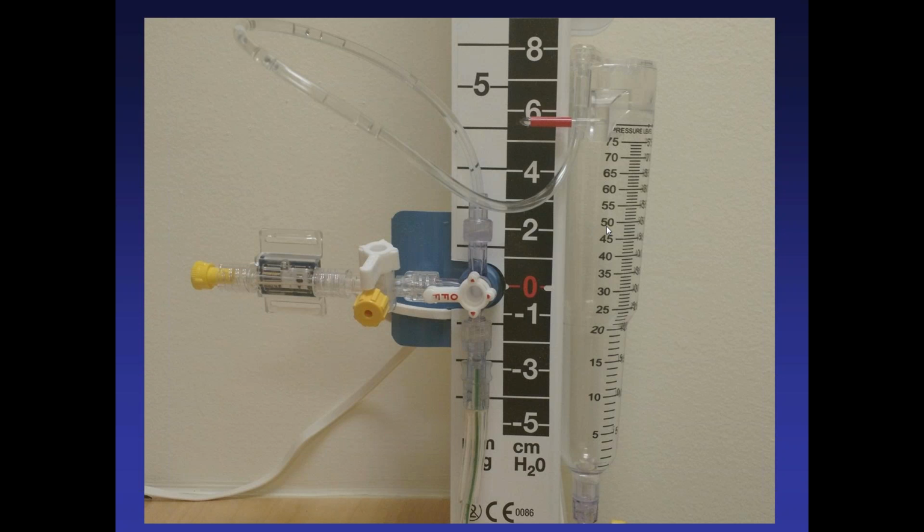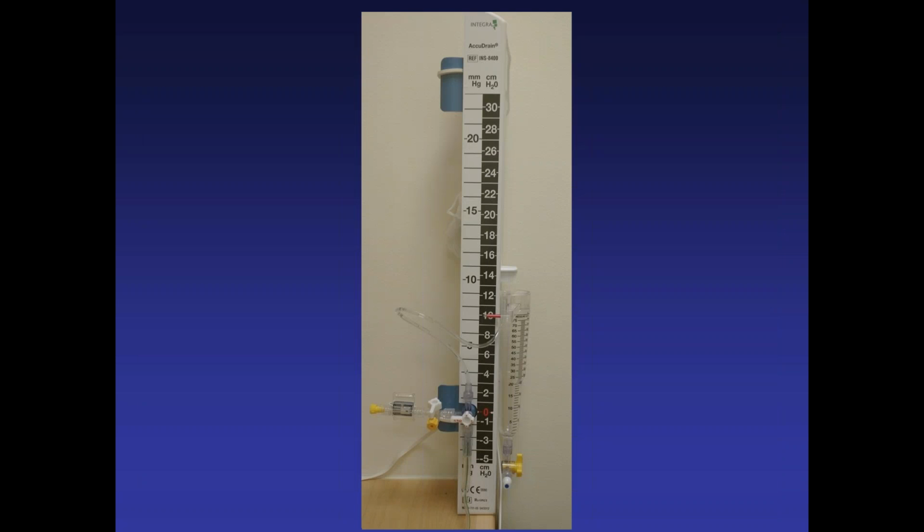Buretrol, you just empty every hour then? Yeah, the nurses are supposed to empty it every hour or two. That's the whole point of this, is that they can do short-term measurements in this. And then there's a bag that connects to the bottom of this for long-term storage. And they don't empty the bag until it's filled up. It's just the fewer times you access the system and open it to the outside world, the less opportunity for developing infection.